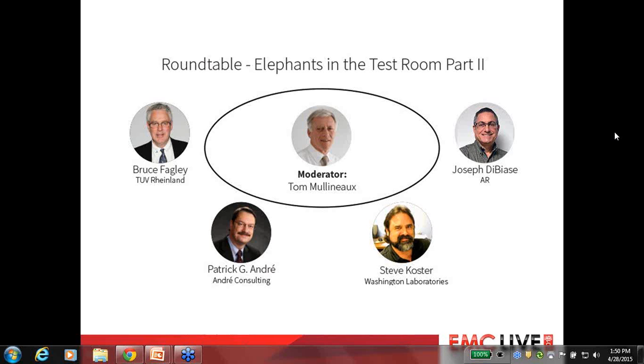This is Bruce. I just had a comment on that. I think that part of the problem here is that the ACIL study, or some of the studies that we've done so far, have proven that there's a big discrepancy, especially down at 30 megahertz. So how can you proceed with an accreditation scheme when you have 30 dB of discrepancy between labs? There's got to be work done to get this to the point where we are much more consistent between labs before the accreditors can start working on this, I think.